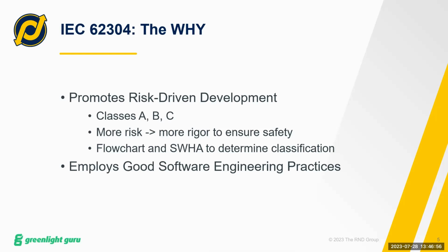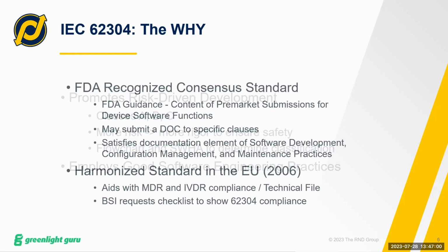So that's the thing that I like about it, is that it uses those things that we're all accustomed to. Another reason that you want to use it is because it's an FDA recognized consensus standard. So it's called out even in the guidance document, the content of pre-market submissions for device software functions, as you are able to use it for part of your submission.